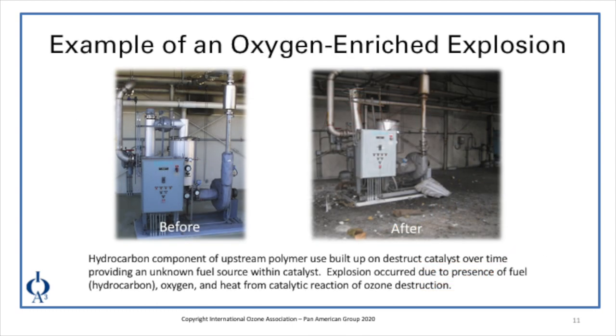One example of an oxygen-enriched explosion occurred at an ozone treatment plant. On the left-hand side you see an ozone destruct system before the explosion, and on the right you see it after, with debris scattered around. What happened is that hydrocarbon components in the polymer being used in upstream processes built up over time on the destruct catalyst, ultimately providing an unknown fuel source. The combination of those hydrocarbons, the oxygen component of the off-gas, and the heat from the catalytic reaction in the ozone destruct system fulfilled all three components of the fire triangle, leading to an explosion.